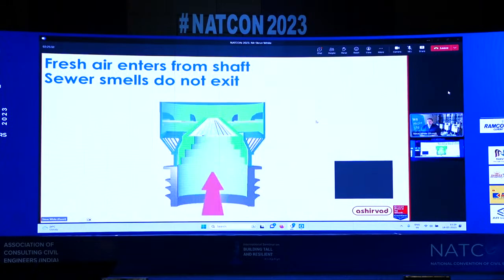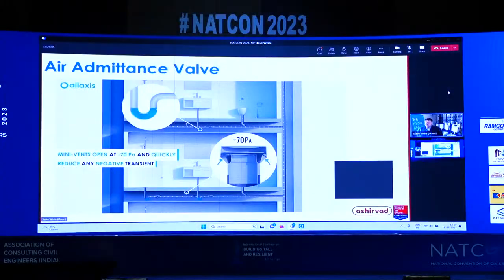And then what we use for bringing the air into the system is what we call an air admittance valve, which is essentially a pressure relief valve that opens at 7 millimeters and admits air in one direction, but does not allow any smells or gases to exit the system. And we typically install these in India every 3 floors on the stack. It's designed to open at 7 millimeters, 70 pascals of negative pressure, well below the threshold of 400 pascals or 40 millimeters water gauge, and it just puffs a little bit of air to replace the air that's been drawn out as it's sucking down the system.